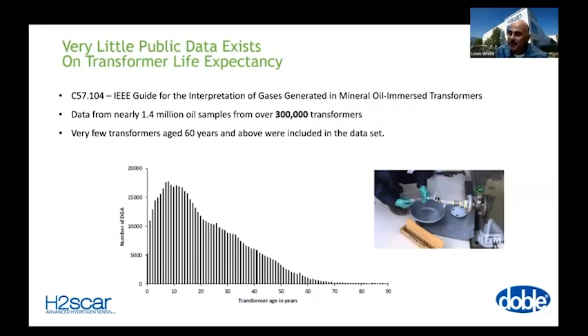So the interesting thing is, if you look at the 300,000 transformers in the IEEE data set, you notice that most of the DGA samples are being performed on transformers in the 5 to 20 year range. After the 20-year point, you start seeing a fairly rapid drop in the amount of samples available from transformers that are 20 years and older. As you get out to 30 and 40 years, the trend continues down. And once you get out to about 60 years, there are very few transformers being sampled, at least in this data set, that are above the age of 60.